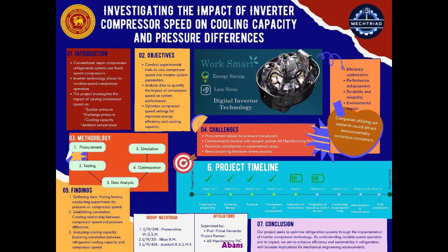Our project explores the influence of inverter compressor speed on cooling capacity and pressure variations, focusing on optimizing performance and energy efficiency. The immediate tasks include calibrating the instruments to ensure measurement accuracy and investigating the functionality and integration of the sensor and control system.